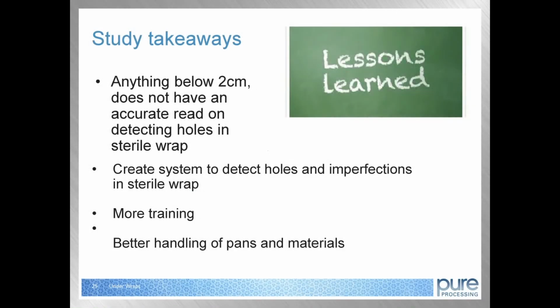What we've learned from the study that was done by the Clinical Orthopedic and Research Center is that in determining defects between 2 centimeters and 5 centimeters, we're accurate about 56.1% of the time. And anything below 2 centimeters, we don't have an accurate read on defects or holes in the sterile wrap. What we do know is that we do not have a current method for assessing sterility, and it is not accurate. So how do we fix that? And what do we do when handling pans so that we don't get holes, and to prevent holes from going from sterile processing up to the OR?